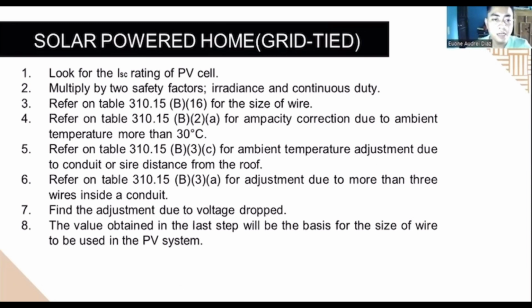First, look for the ISC rating of PV cells. The ISC is the short circuit current. Second, multiply by the two safety factors, 125% and the continuous duty. Refer to the table of 310.15, multiply by B and 16 for the size of wire.